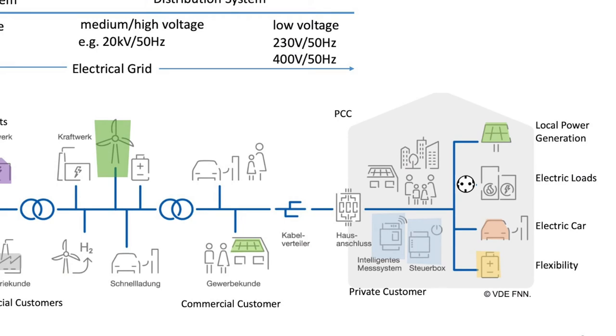20 kilovolts is about 50 times the 400 volts of our low voltage system, so assuming the same currents in the medium voltage system we can transfer 50 times the power. Higher voltage allows higher power to be transferred and larger loads to be connected, as shown here: fast charging stations, larger batteries, wind turbines, smaller power plants, hydrogen production sites — all those systems can be connected to the medium voltage side, along with many low voltage feeders like our house.